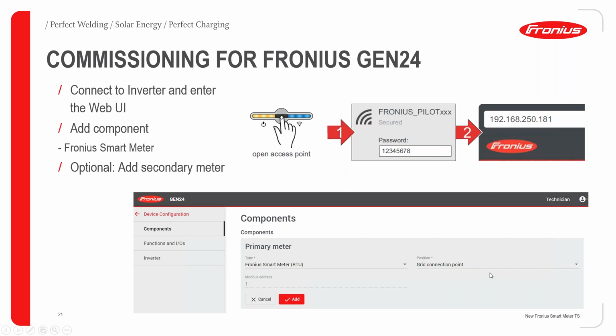Is it in the grid connection point, that is the feed-in point, or is it in the consumption path? If you're measuring any special load, you have to do it, and then you have to add it, and then you have to give the Modbus address. That's very important. Same way, if you are using multiple smart meters in one system, you have to change the address. By default, all the smart meters are addressed as one. If you're using just one smart meter, you don't have to do anything. You can just click add.